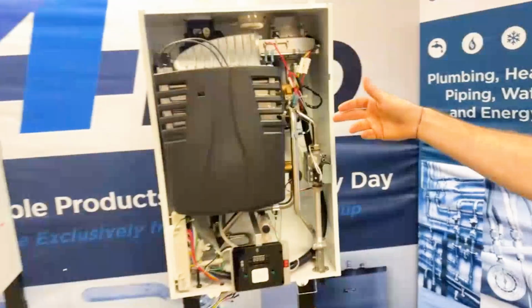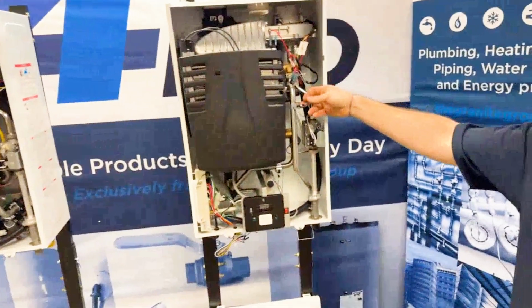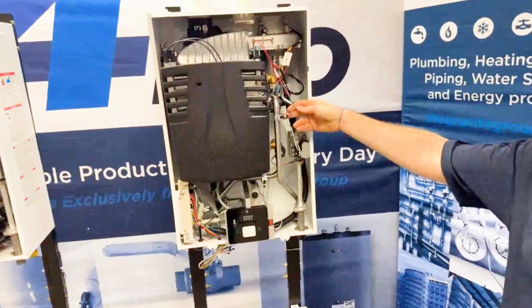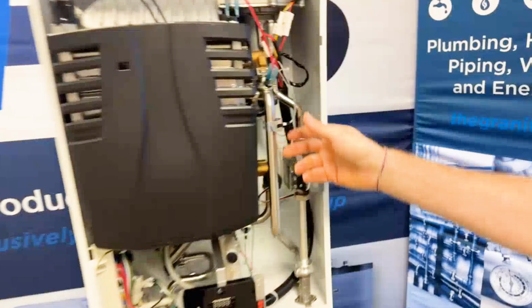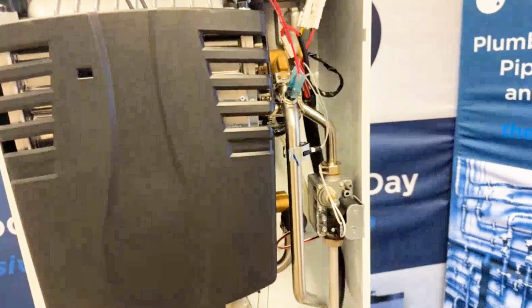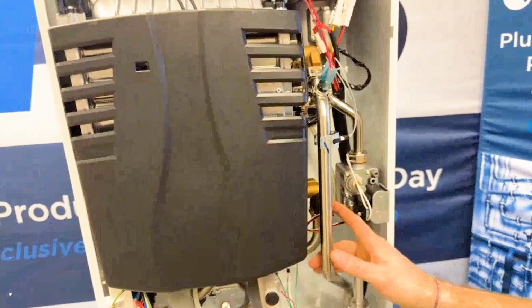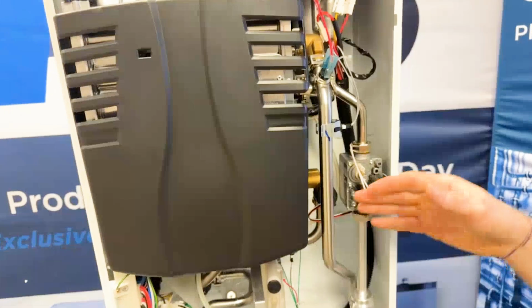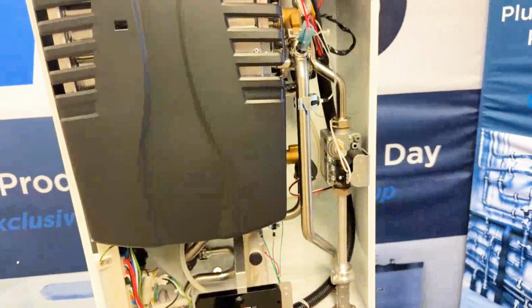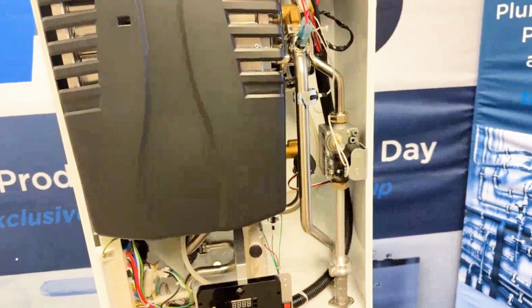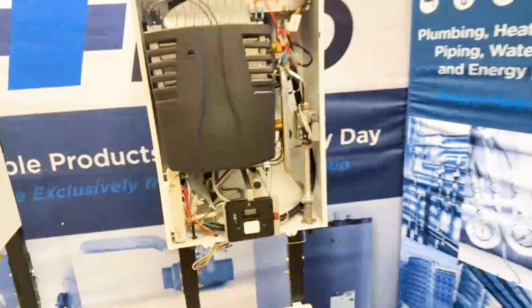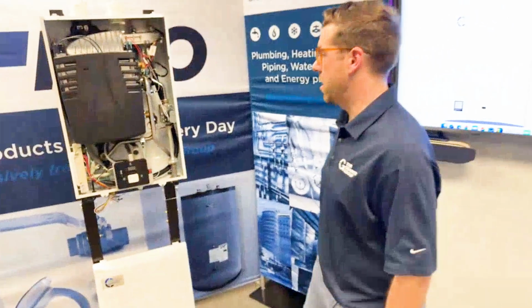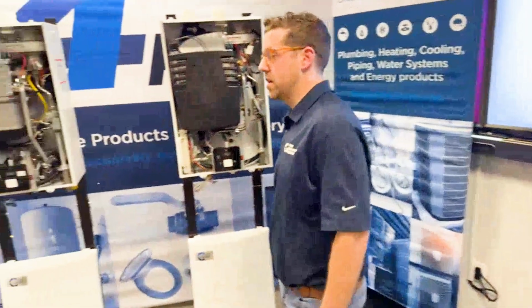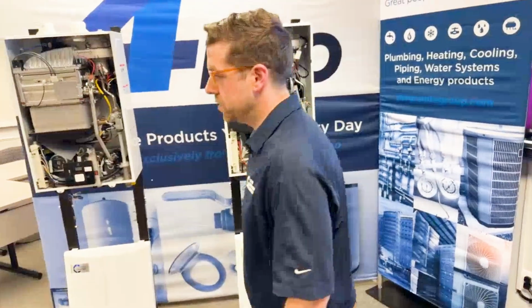So let's say we are replacing one of these down the road after a few years in the field. We're not going to drain the system down to replace the temperature sensor. If the pressure sensor were to fail, you would be draining the boiler down, but that's your only wet sensor there, the pressure sensor. So super helpful when you're trying to make a repair at this time of night, in the dead of winter.